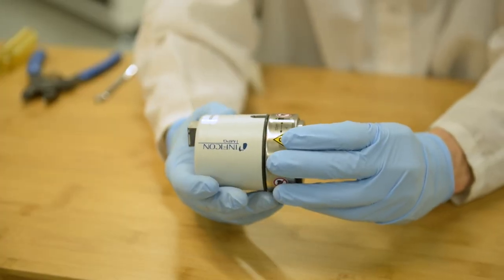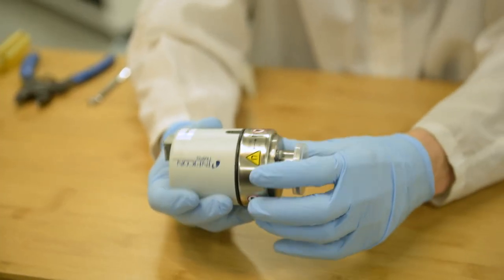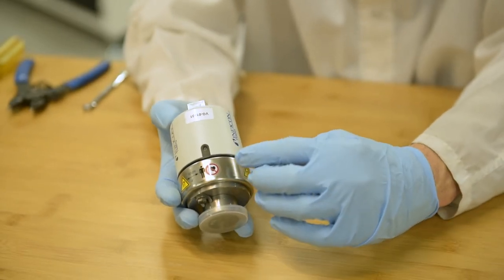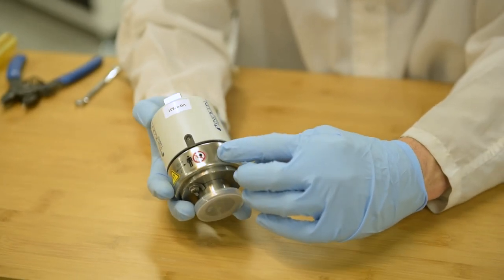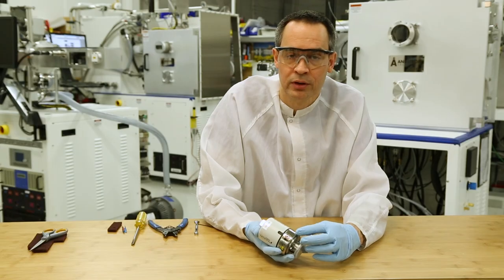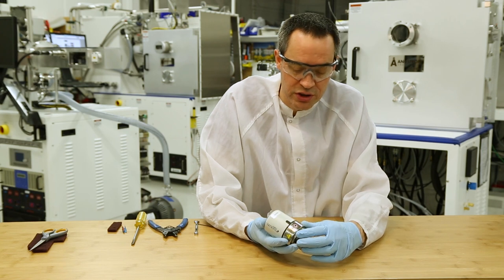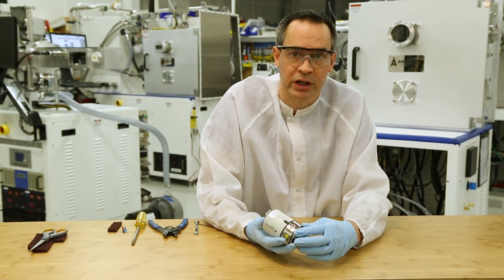Most cold cathodes have a very strong magnet. This particular gauge has a warning symbol on it. If you find that you're susceptible to strong magnetic fields, perhaps from a pacemaker, then consideration should be made for your safety in terms of working with the gauge.